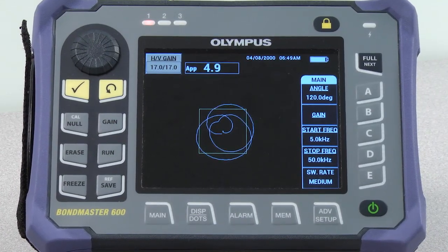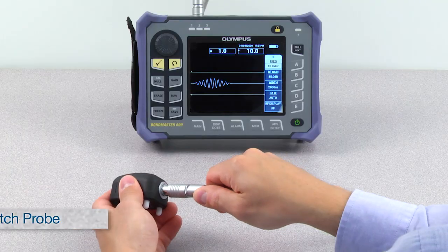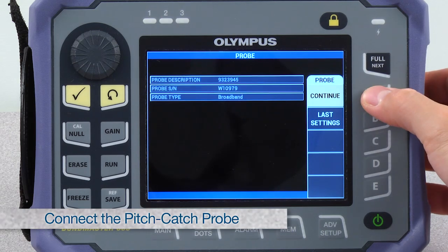Configuring the Bondmaster 600 for general-purpose disbond detection is very easy. Simply connect the pitch catch probe and press continue.